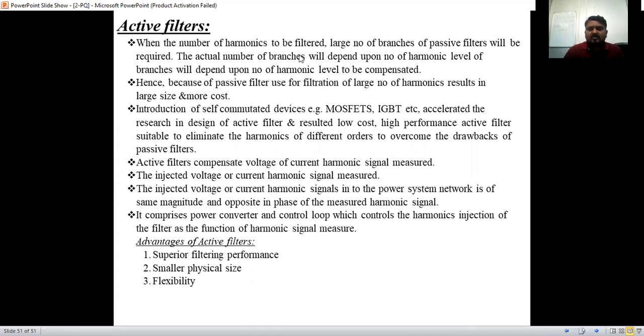So when the number of harmonics to be filtered is large, a large number of branches of passive filter will be required. Why? Because different circuits are used for different harmonic orders. For the first order it is different, second order different, third order different, fifth order different. So based on the order, if multiple order harmonics are present in a system, we have to use multiple branches or multiple filters.